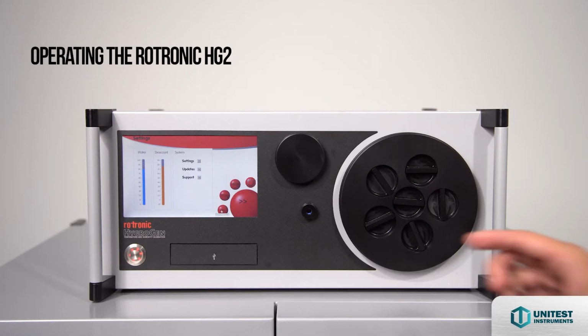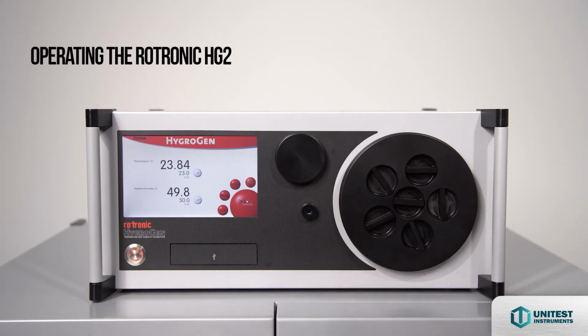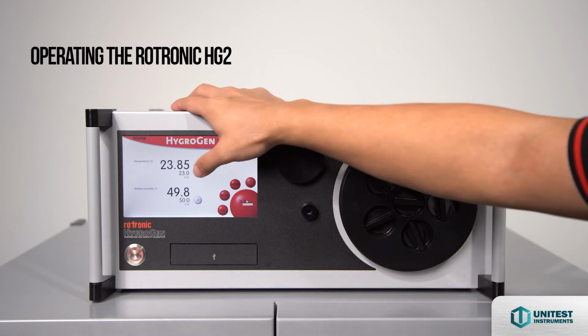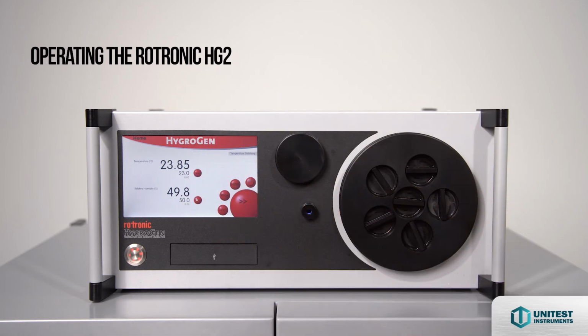Once these parameters are checked, proceed to the main screen and tap on the set points to open up a pop-up window where you can change the required set points. Once the set points are assigned, tap on the circular status button to control the parameters to the set points required. You can choose to operate each parameter independently. When off, the control buttons are grey. When on, but not stable, the control buttons are red. When on and stable, the control buttons are green.